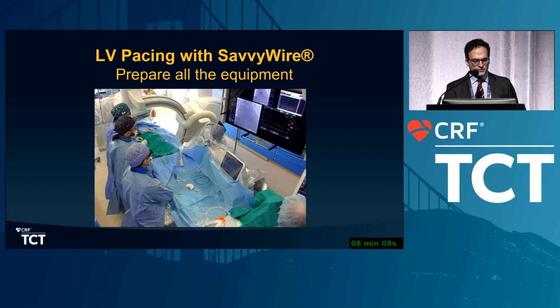So just before putting the wire inside the ventricle, you need to have the grounding, the needle or whatever you're using, all the cables. You can see the SavvyWire here, the monitor, the pacing, everything ready in case that the patient goes with an AV block, so you can respond very quickly. The main advantage of this wire is that it's isolated, so you don't have to put any catheter or anything. So you just put the wire, and you can immediately pace the patient. So it's very, very safe.